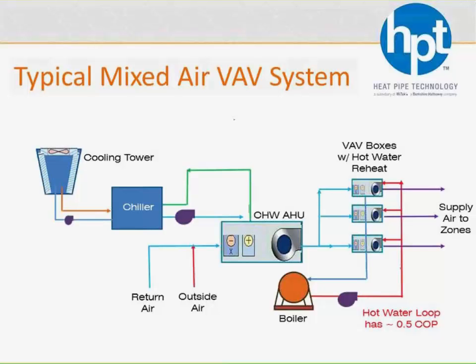Downside here, one is that you've got to add the reheat to make it comfortable out there, but reheat is not cheap. You do have to pay for it, and unfortunately hot water loops are not very efficient. I mean, your typical boiler or your hot water loop is going to have a COP of about 0.5, meaning that for about every unit of energy you're using to get that hot water, you only get about half of that out of it. And if you're using electric heat for that reheat, it's even less efficient. So it does cost you some money. Also, those VAV boxes, because they're delivering a combination of outside and return air, they won't close completely. They're always going to be delivering air to the space, and you've always got to make sure you're having enough ventilation air out to the space, and that's a result of that air being combined. Better safe than sorry, make sure you deliver some ventilation air out into the space.